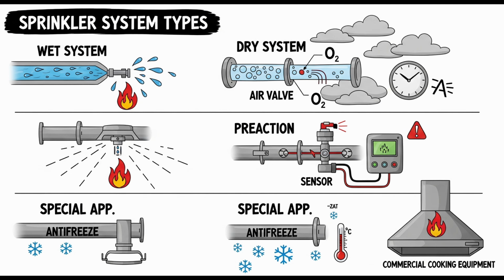So the standard room sprinklers overhead aren't considered sufficient on their own to handle a potential grease fire erupting on the cooking line or inside the hood and ducts. Not on their own, no. Grease fires are intense, can spread rapidly into the exhaust system, and need suppression applied directly at the source. So you need dedicated protection, specifically targeted at the areas where grease accumulates and fires are most likely to originate and spread. Inside the exhaust ducts, at the hood exhaust duct collars, where the hood connects to the duct, and within the hood exhaust plenum chambers, the space inside the hood above the filters. Okay, target those specific hot spots.